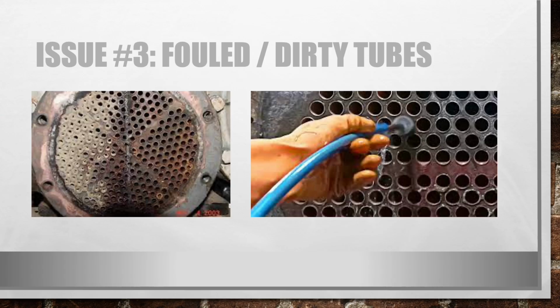The picture on the left there is a machine that's extremely fouled. When you pull an end bell off, it should look similar to the machine on the right. Granted, you're definitely going to have some debris that builds up in there over the cooling season, but it should not be fouled up to that extent. So in the spring or in the wintertime when they're punching the tubes, you really should only have to punch tubes once a year unless it's a really strange condition. If it's a specific application where they are running really nasty water through it all the time and they can't prevent it, maybe they need to punch the tubes more than once a year, but it should only really need to be done once a year.